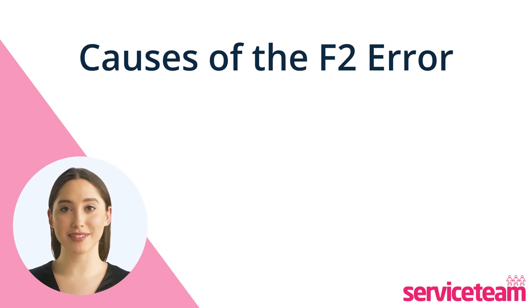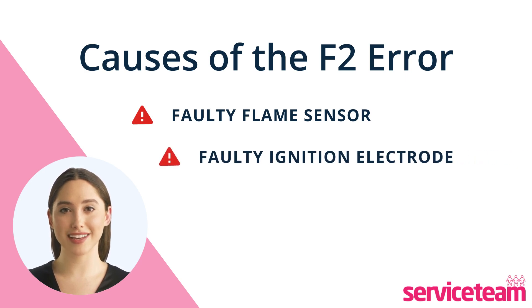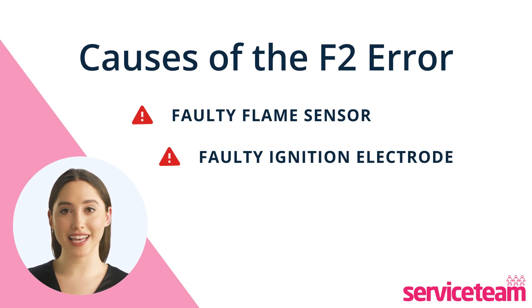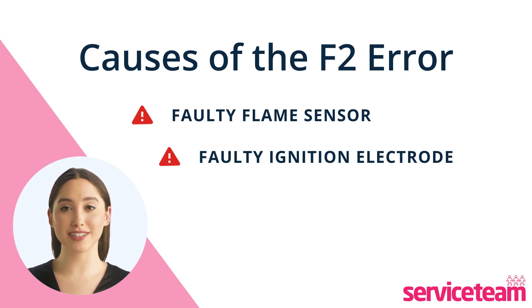Let's understand what causes the F2 error. If your boiler has a faulty flame sensor because it's dirty or not working right, it might display the F2 fault code. The second cause is a faulty ignition electrode, which is essential for the combustion process in a gas boiler. It is typically located near the burner and creates a spark to ignite the gas. If it's affected by dirt, misalignment, physical damage, a faulty control board, or insufficient voltage supply, it triggers the F2 error.